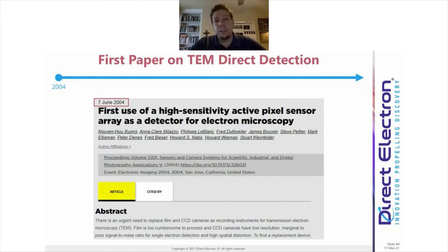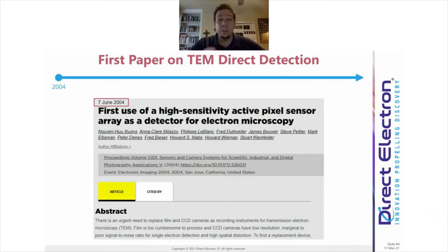The very first paper showing Direct Detection for TEM came out in 2004. This was a collaboration between Lawrence Berkeley National Lab, UC Irvine, and UC San Diego. They were using a CMOS-based active pixel sensor to directly detect electrons. This is different than the previous strategy for digital cameras, which was to use an indirect detector that was scintillator-coupled — the electron would be converted to light first, and then you'd image the light. That conversion process caused a loss of resolution and a loss of sensitivity.